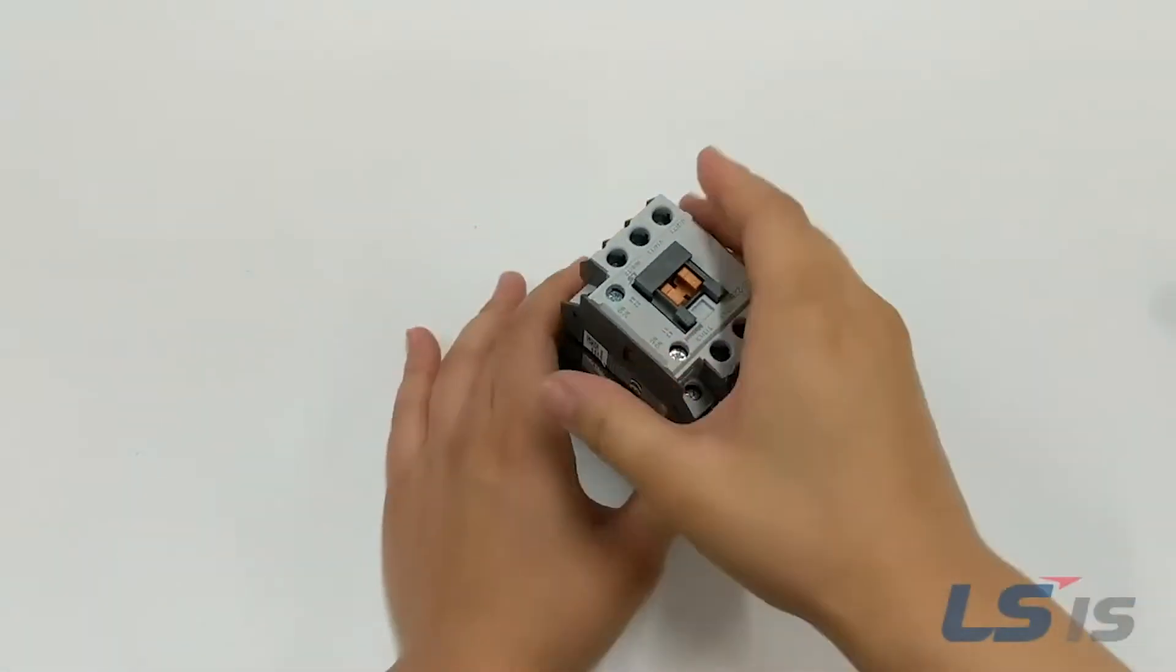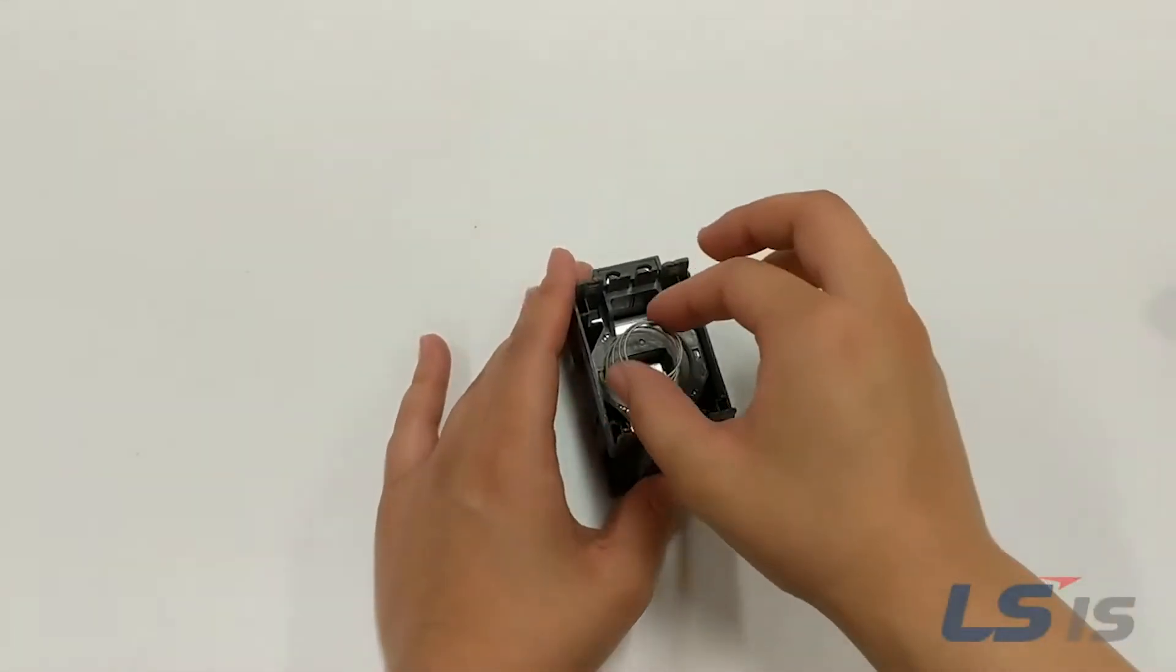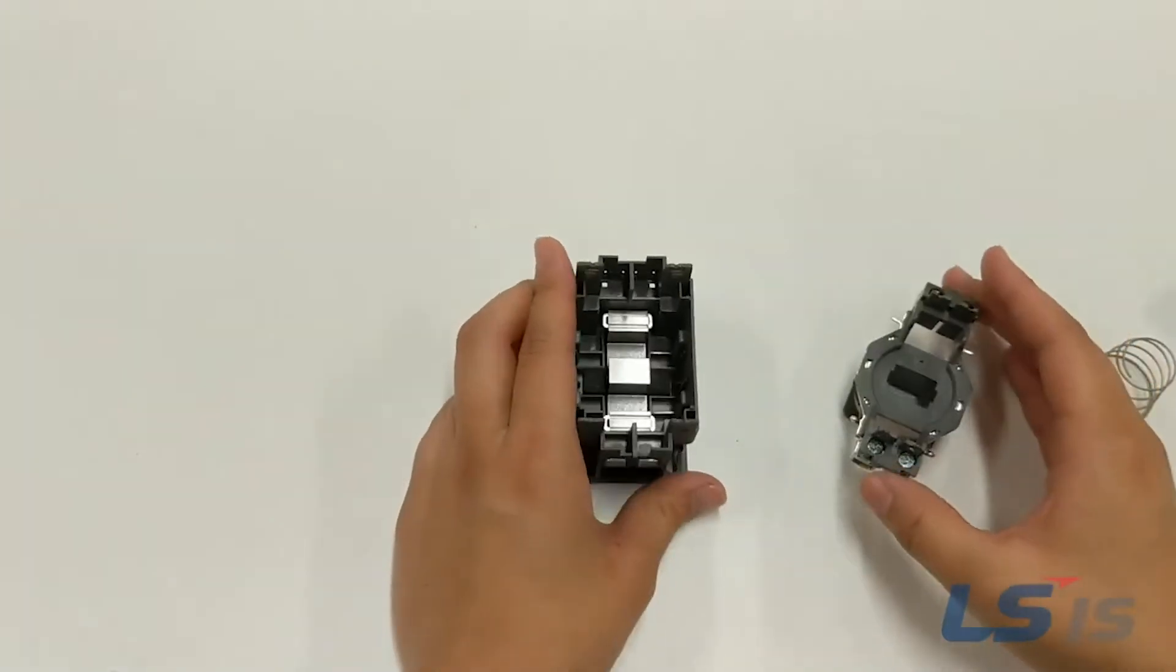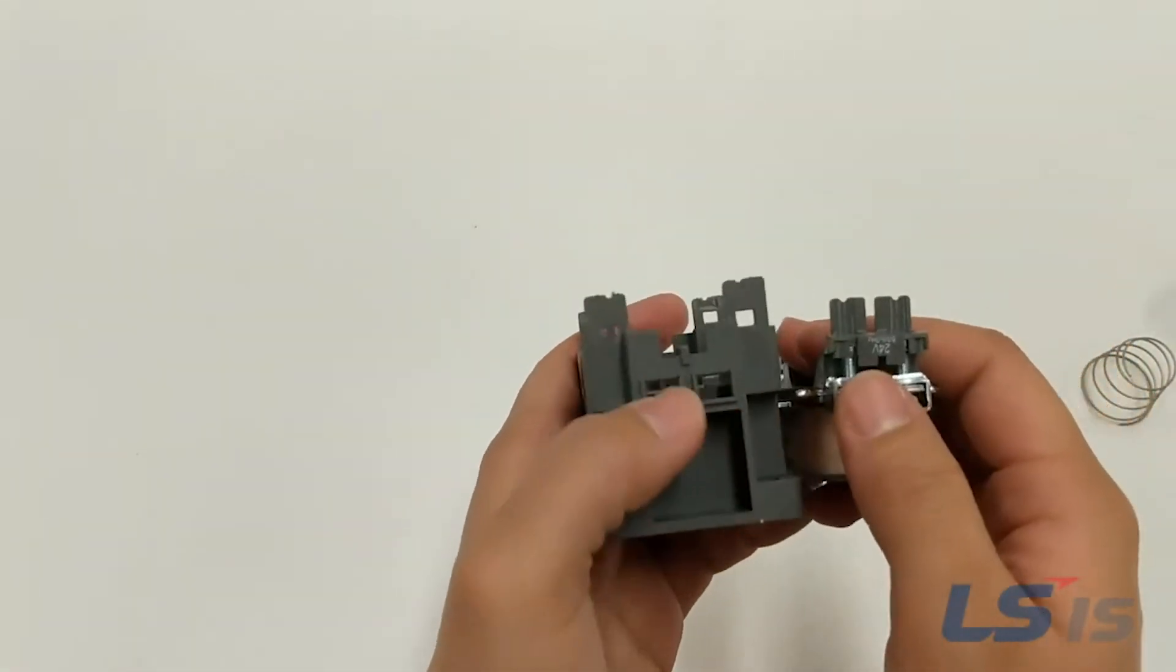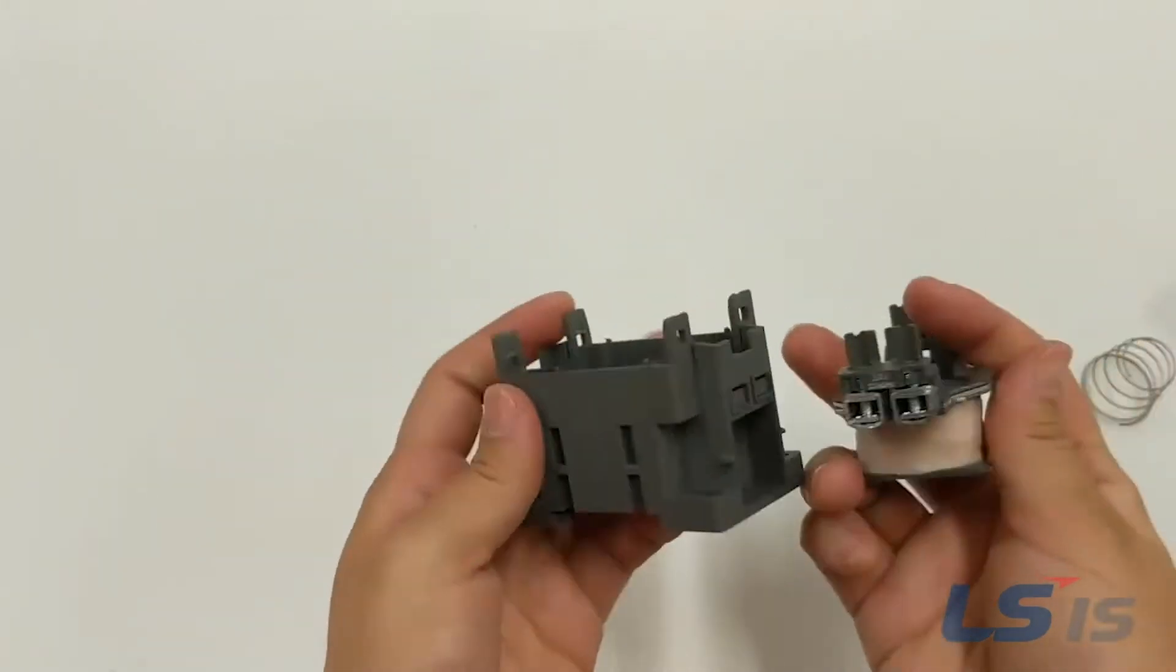Then remove the top half and the spring and then we can lift the coil out and slide in the replacement coil. Make sure that the notch on the bottom half aligns at the side with the indent so that the coil is placed with the right orientation.